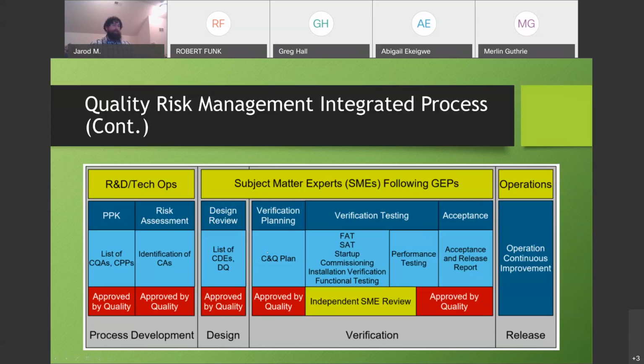And so putting a lot of that effort into the planning phase and focusing that on all of the information from the quality by design in the previous phases, to then move into verification testing, where that's go forth and be fruitful in FAT, SAT, commissioning, startup, and functional testing.